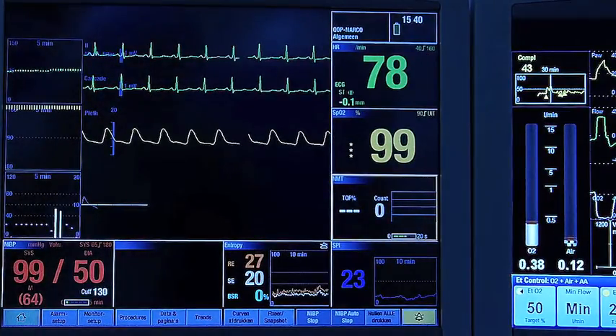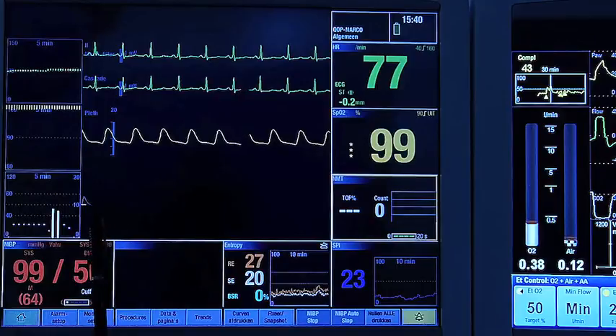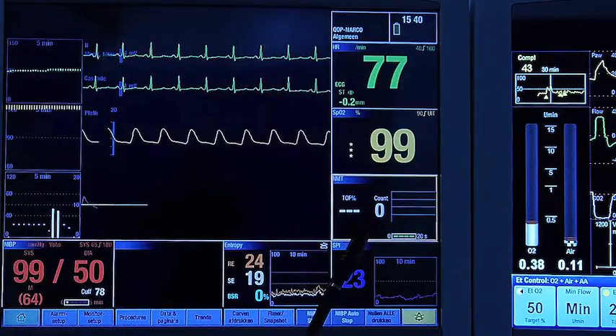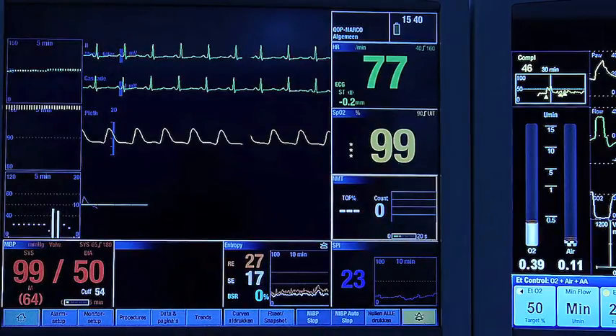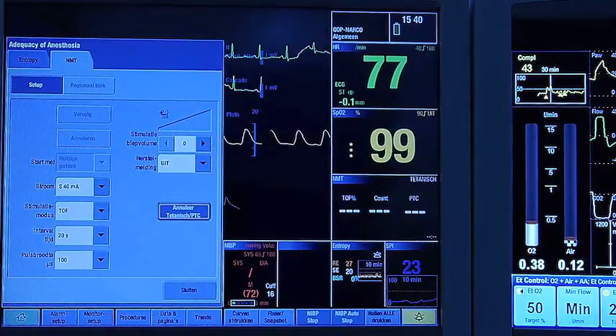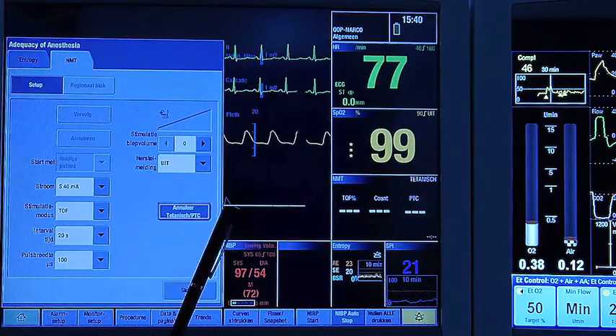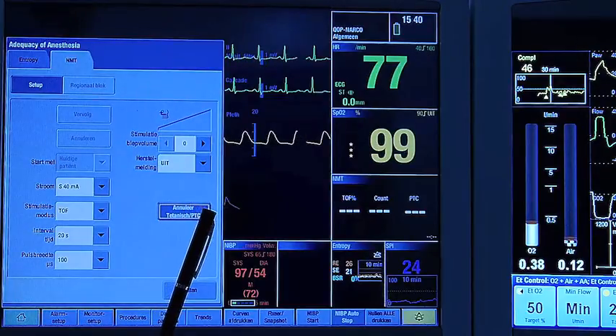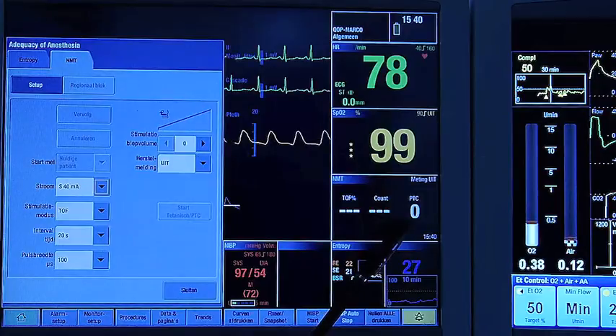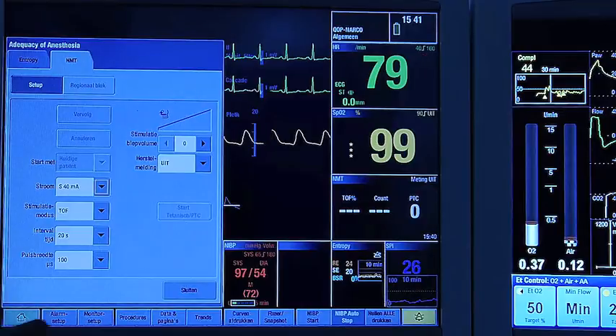We changed the position of the electrodes, placing them farther from the wrist, and adjusted the current. Now with a train-of-four stimulation, we see no answer at all — a TOF count of zero. Checking the PTC count: after tetanic stimulation, the PTC count is also zero. This confirms we were in an extremely deep block, yet the incorrect electrode placement had falsely indicated a TOF count of three or four.